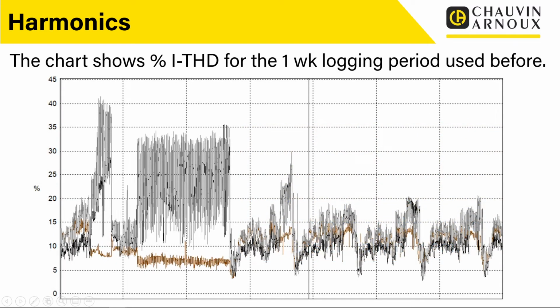So giving you a bit more of an example of a bigger installation here. This is going back to the installation that we did the 1 week logging on. And you can see here, this is the same period. This is effectively the same graph, but in this case, we're showing percentage current THD. And you can see the same sort of alterations over the days. So you can see where the days fitted in there.